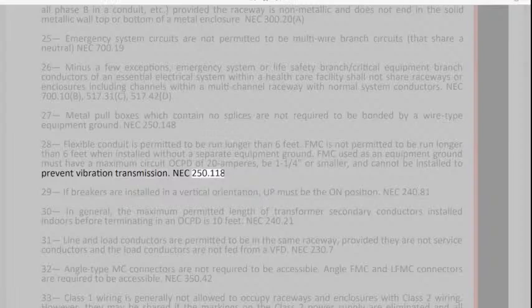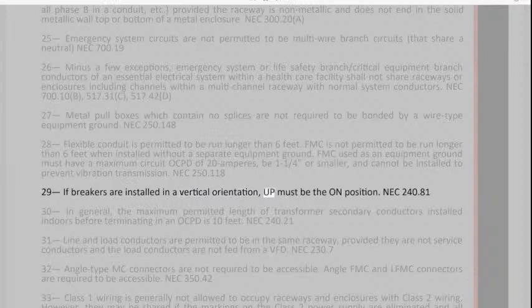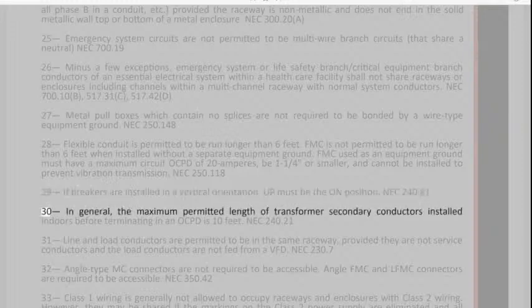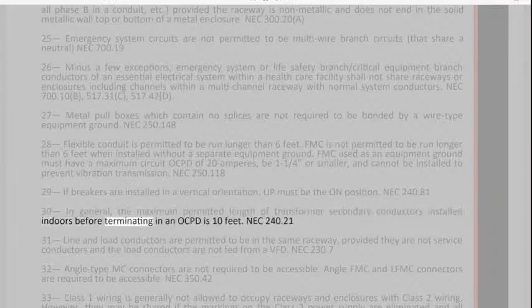250.118. 29. If breakers are installed in a vertical orientation, up must be the on position. NEC 240.81. 30. In general, the maximum permitted length of transformer secondary conductors installed indoors before terminating in an OCPD is 10 feet. NEC 240.21.